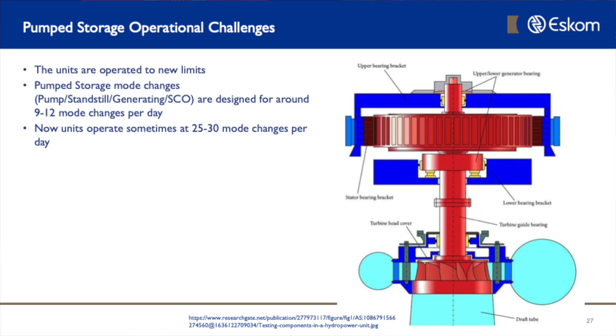Now, when these plants were designed, they were designed for an average of between 9 and 12 mode changes a day. But over the last 10 years, due to load shedding and supporting the grid, with the system operator having the pump storages come in and go out as needed, we were looking more often than not at units running between 25 to 30 mode changes a day.